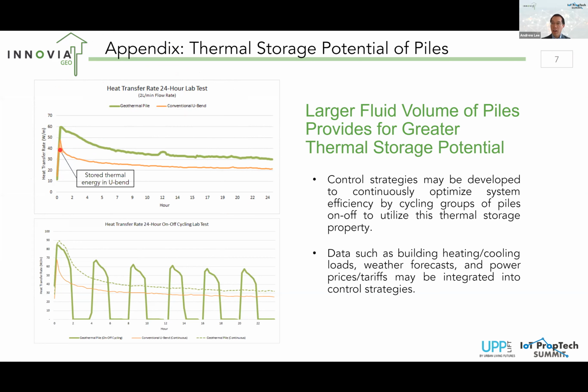And so you draw that heat in the fluid first, and then it starts exchanging heat with the ground on a steady state basis. With a pile, there's a much larger fluid volume in the system, and so that stored thermal energy effect is significantly larger. So rather than potentially 30 minutes of higher performance, you potentially get several hours of higher performance through the pile because of that larger fluid volume.